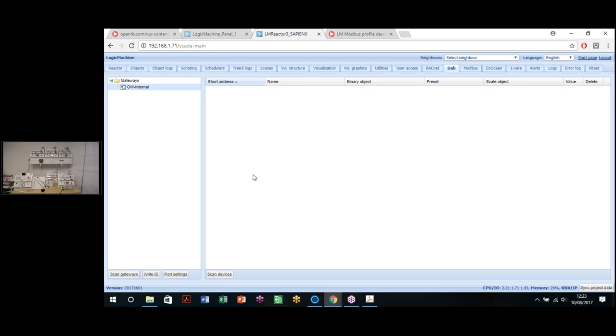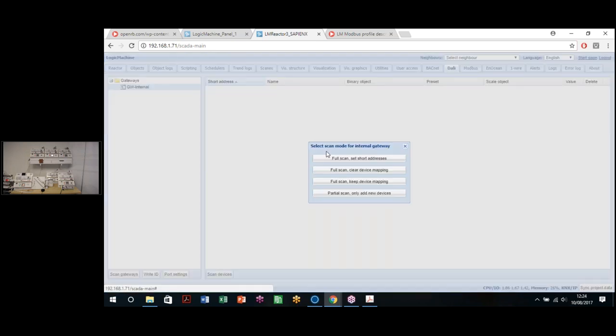It's a very important point that you have to use a certified DALI power source for installing this DALI network. Logic Machine doesn't power the DALI network, so you need a specific DALI power source. Okay, we select the internal gateway and we click on scan devices. We have a few options. We can full scan, setting the short address of the ballast.